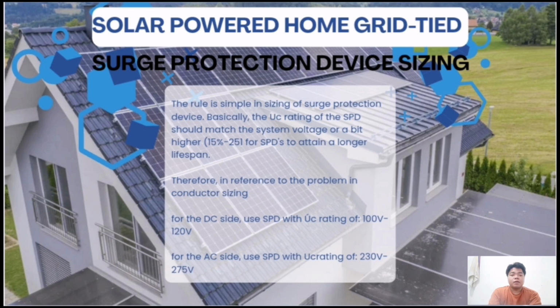Halimbawa, sa low voltage side ng system, pwede gumamit ng SPD na may rating na 100 to 120 volts DC. Sa typical household o grid side naman, mas appropriate ang 230 to 275 volts AC na SPD rating. Ibig sabihin, hindi lang basta pareho ang SPD at system voltage, kailangan may allowance na mas mataas para sa safety margin. Ito ay para maiwasan ang premature failure ng SPD at mapahaba ang lifespan nito.